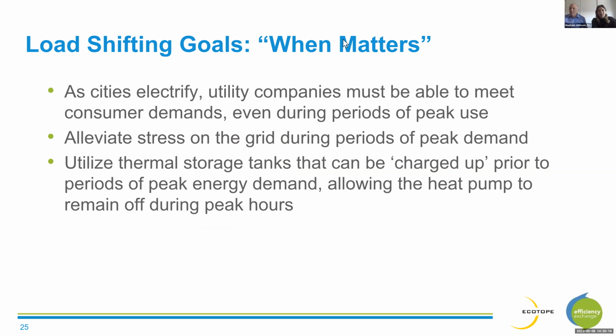Hi, everyone. So as John mentioned, we just went to the Efficiency Exchange in Portland, where we got to hear from utility companies all over the Pacific Northwest and hear about their needs as we electrify the grid. So utility companies need to be able to meet consumer demand even during these periods of peak use. So one of our goals of load shifting is to alleviate stress on the grid during periods of peak demand. And we want to do this by utilizing that thermal storage tank, which can be charged up during our load up period and allow the heat pump to remain off during peak hours, which is when we schedule our shed periods.